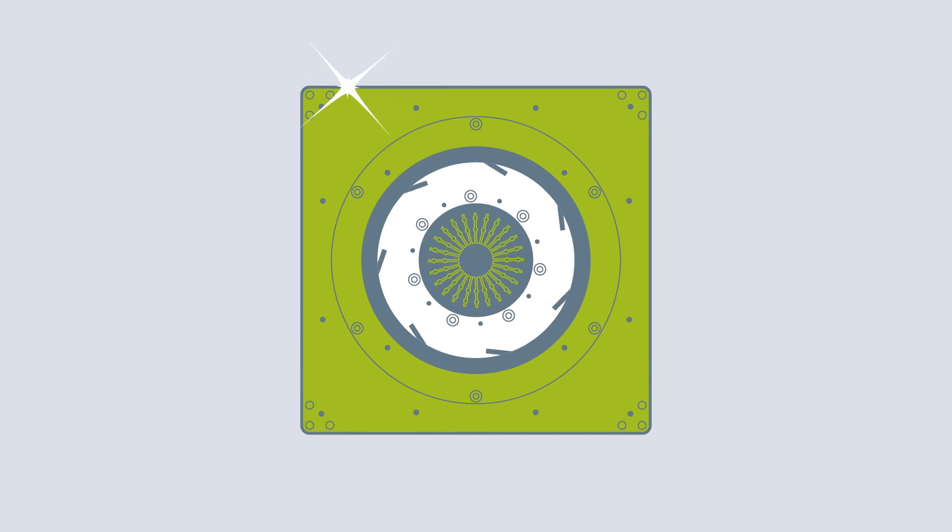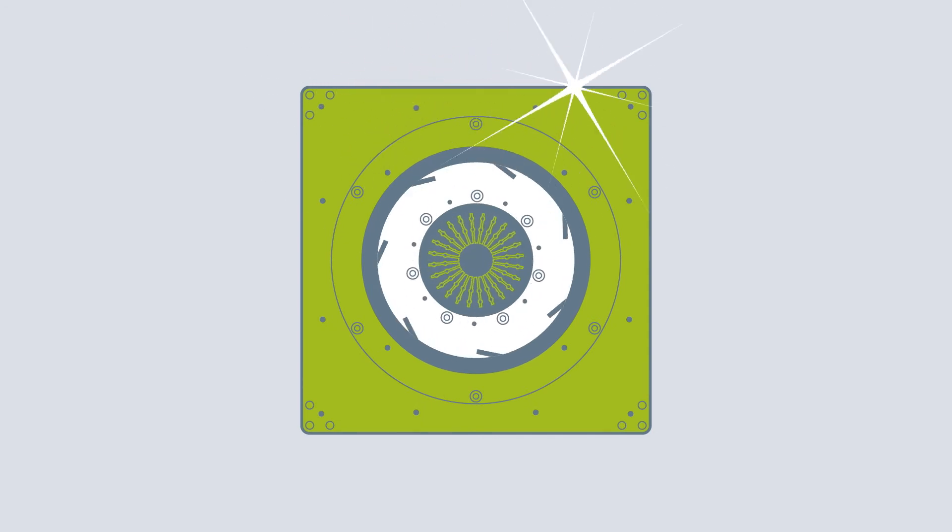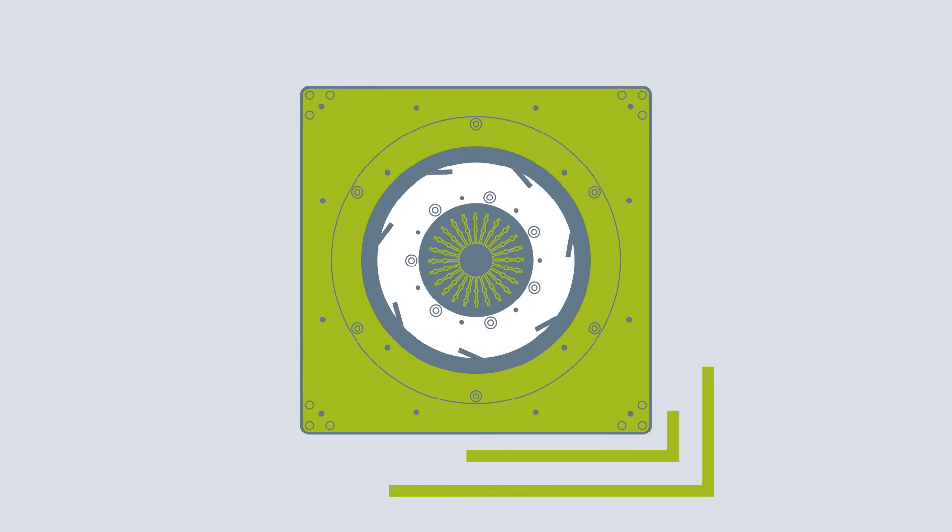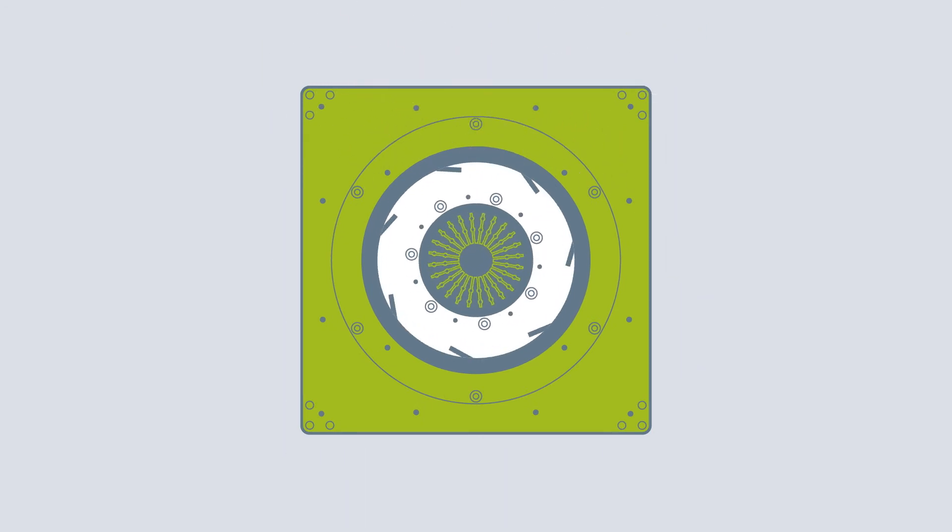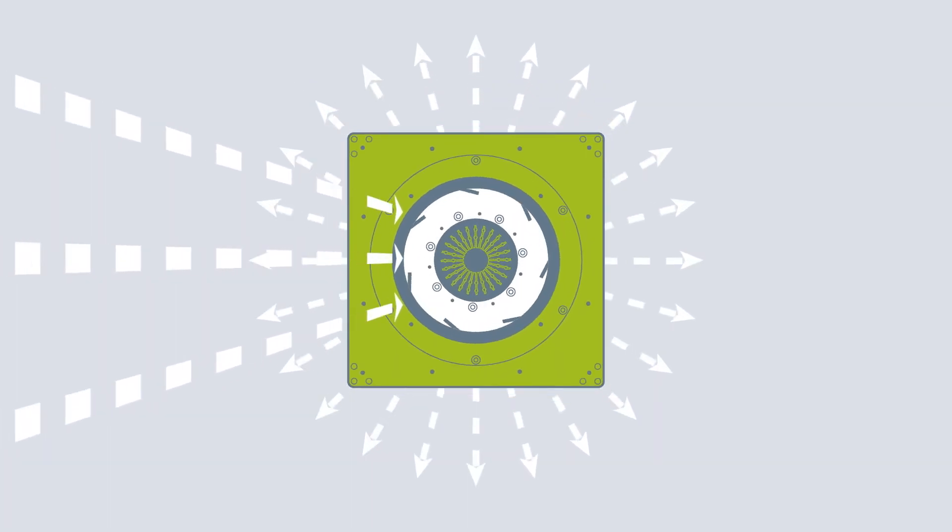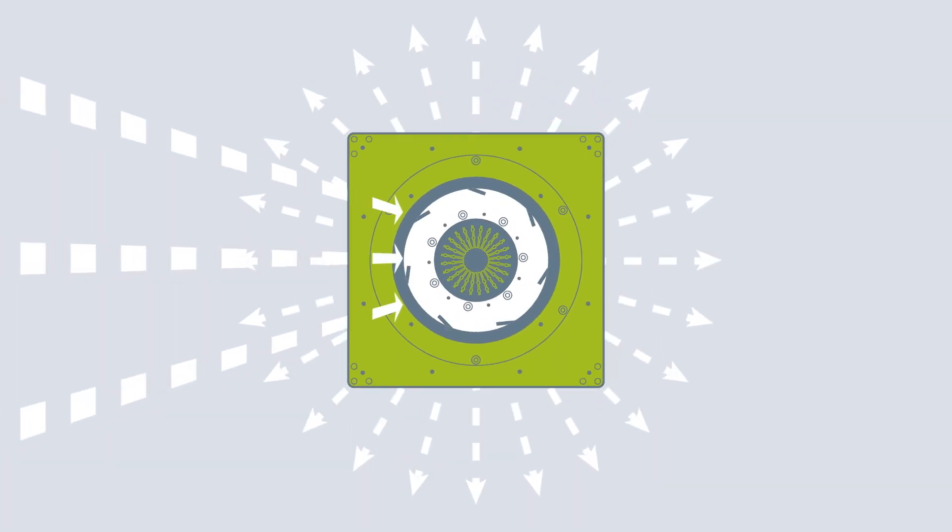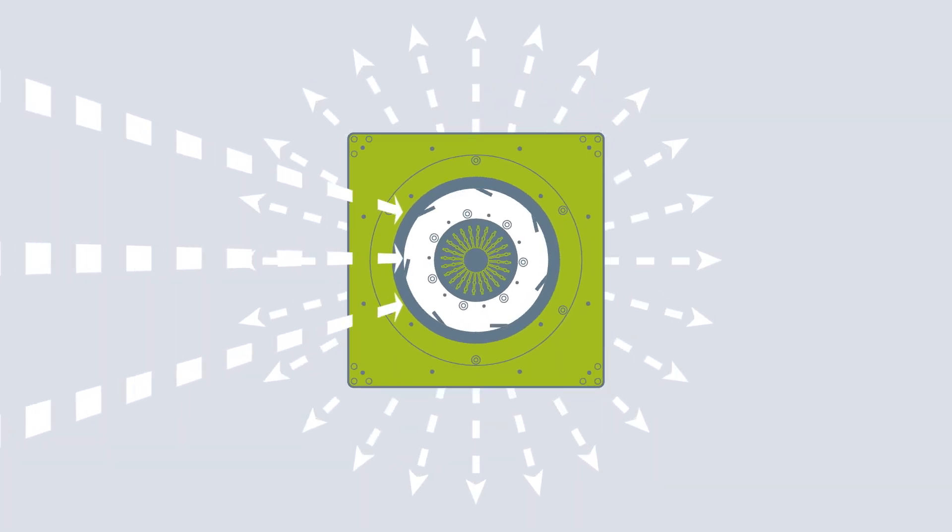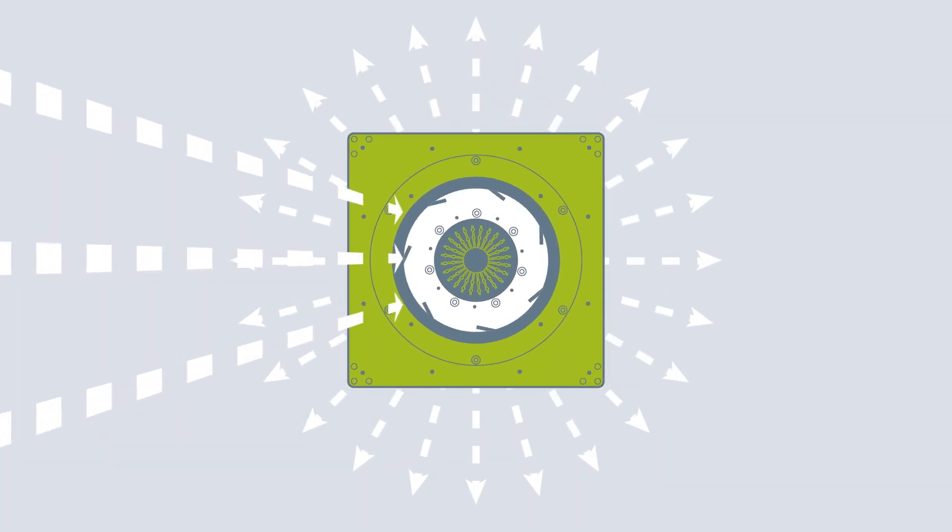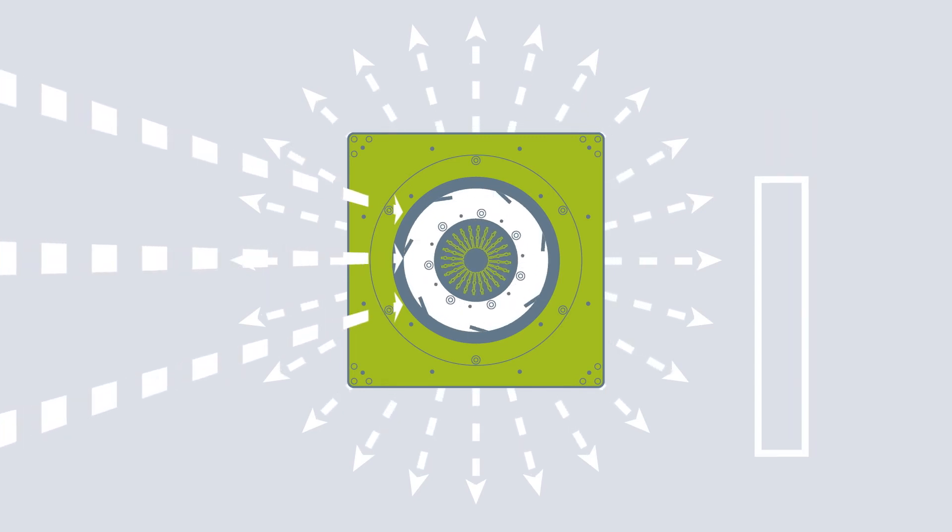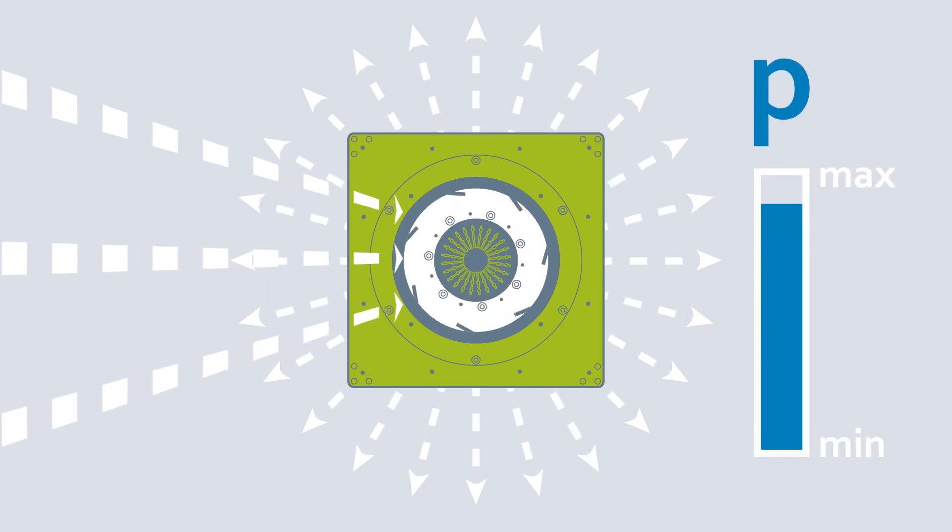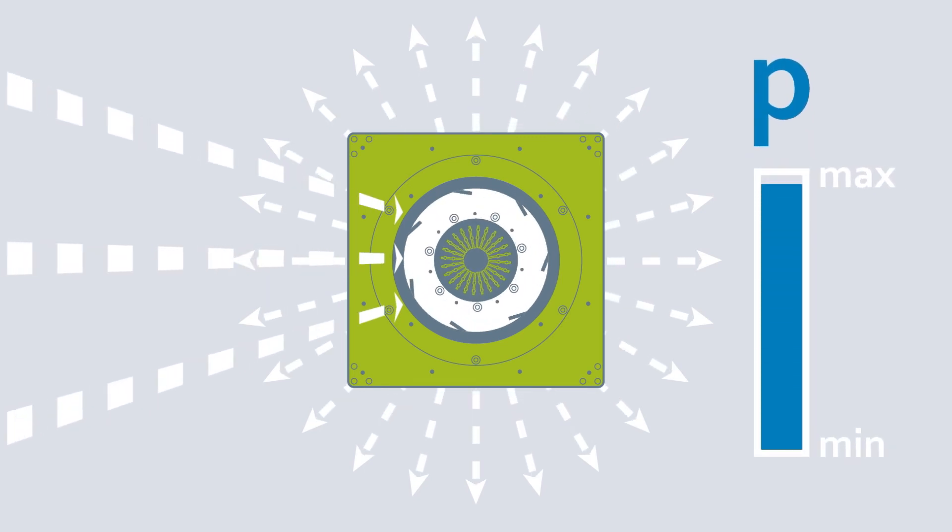Centrifugal fans are therefore usually the choice for ventilation units in practice. In centrifugal fans, the air mainly flows from the center point outward, in other words, radially. Because of this, they generate a higher pressure increase.